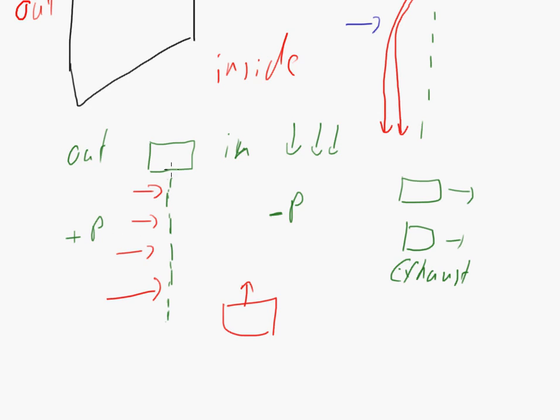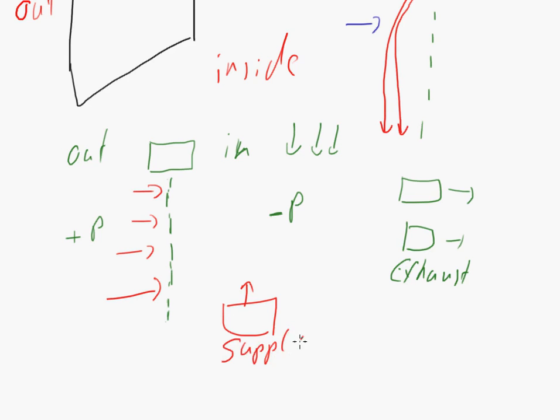And eventually, air from the outside will come in, and basically your air curtain will not be very effective. So that's why always check if you have these huge pressure differentials in your building due to exhaust fans or other factors. Because then you need some supply fan system which supplies your building with air and increases that pressure so it equals more this outside pressure.